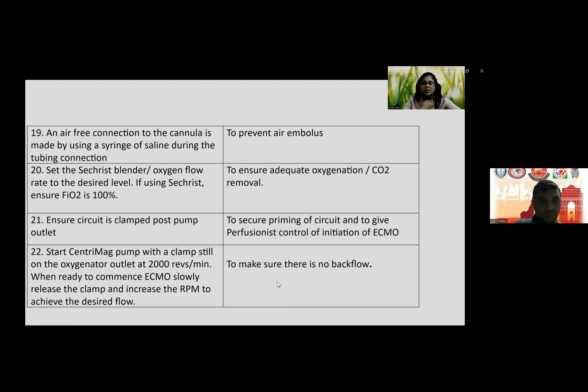And then you start the CentriMag pump with clamps still on the oxygenator outlet at 2000 revs per minute. When ready to commence ECMO, slowly release the clamp and increase the RPM to achieve the desired flow. This is done to make sure that there is no backflow in the circuit, right?